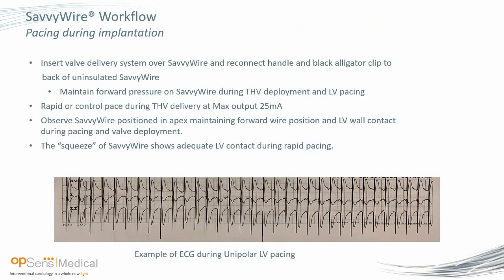So again, the workflow is you check your pacing. You can check it either once your valve's in or beforehand. Again, I like to minimize my steps, so I do it once the valve's in. Once you've crossed your valve and got your gradients, you can then disconnect the transducer on the back, similar to an FFR pressure wire transducer, load your valve on, advance your valve, clip your alligator clip on, check your pacing thresholds, and then go ahead, advance your valve, and deploy in the standard manner. Take the valve out, connect your pressure sensor back onto the back, and measure your post gradients. It's a really, really efficient, seamless workflow.